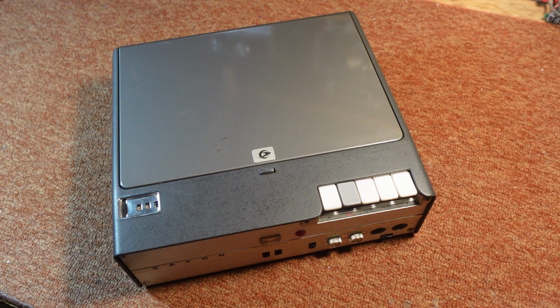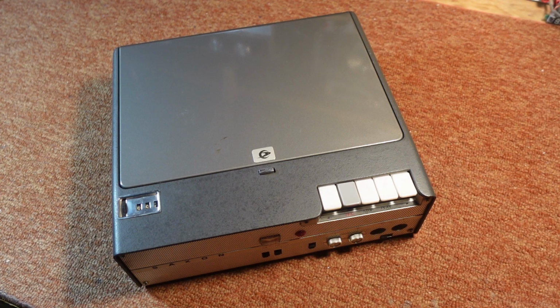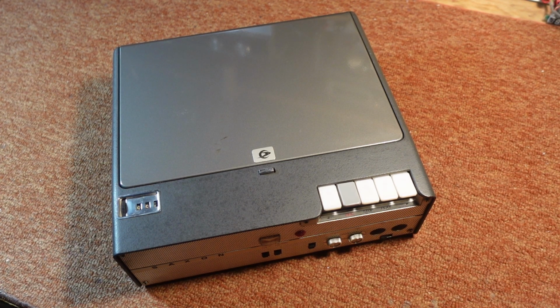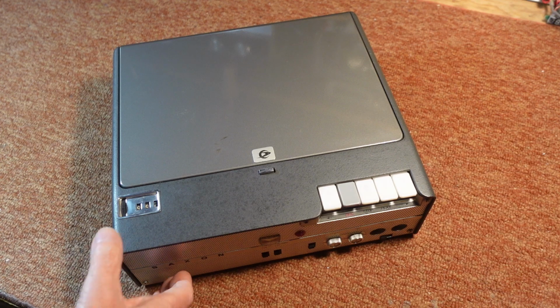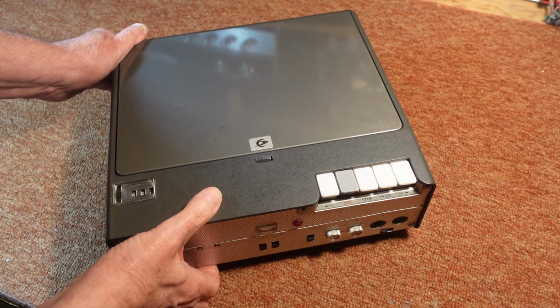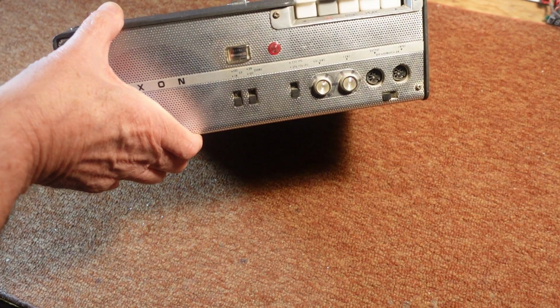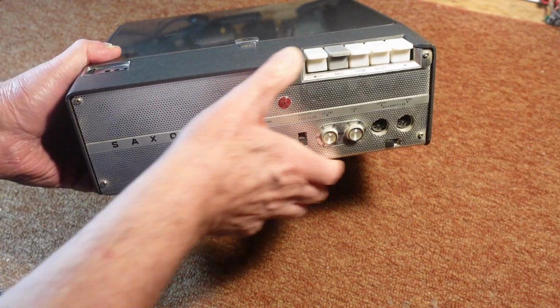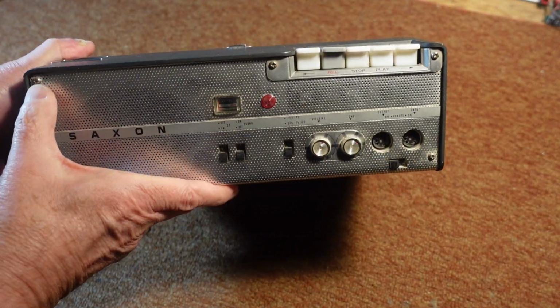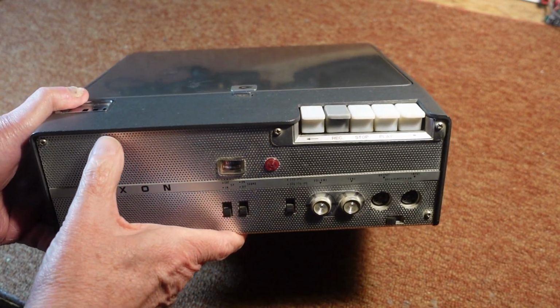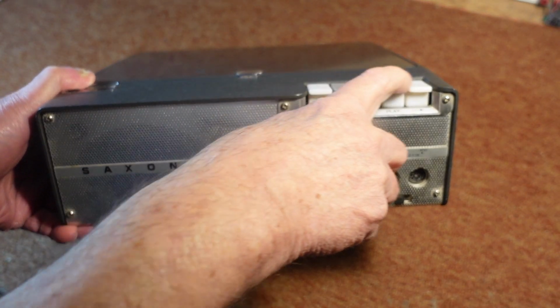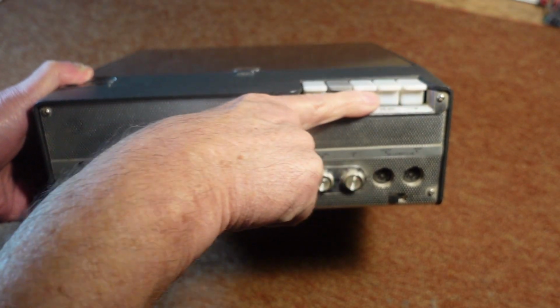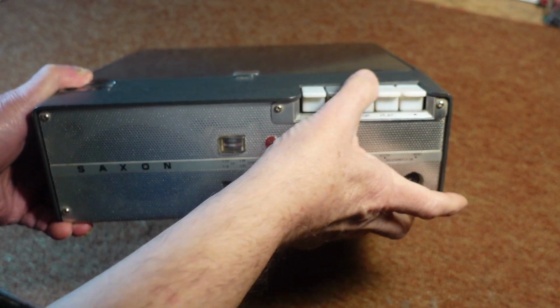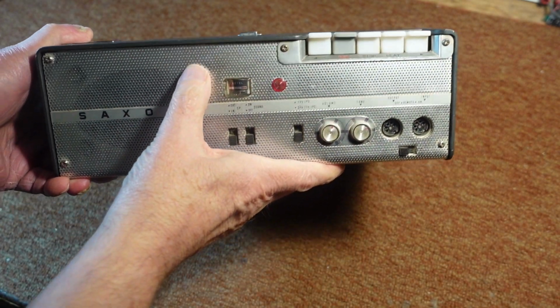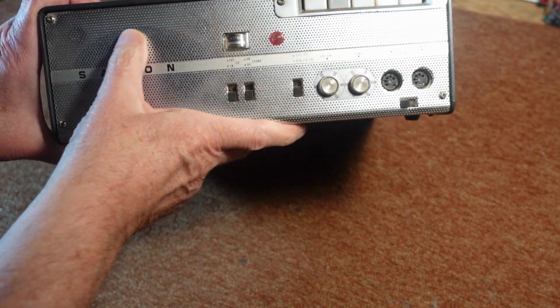Before we do anything, we should do a quick mechanical inspection of the exterior of the machine. Well, the housing looks really good. There's no dings or bangs or dents, and it doesn't look like it was ever dropped, which is a good thing. All of the keys on the functions are straight, so mechanically that looks pretty good. Front panel is in good shape.